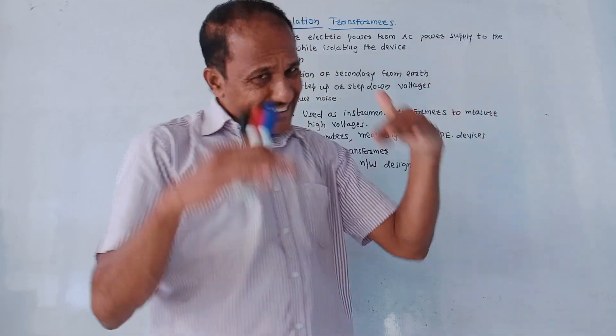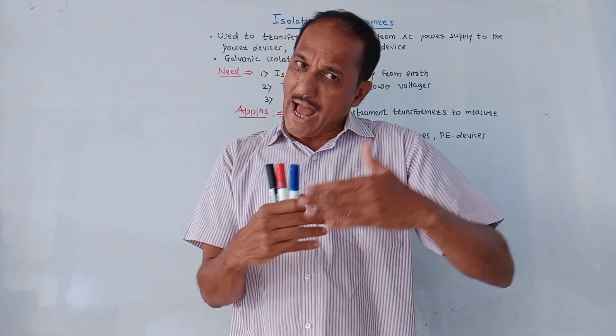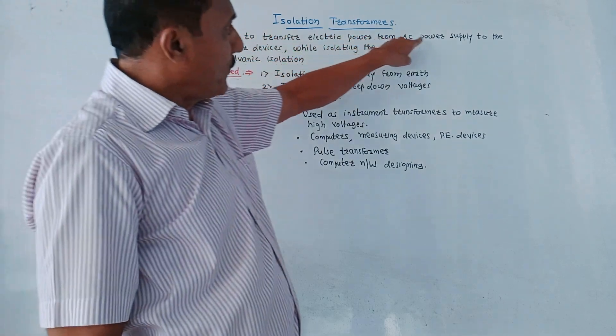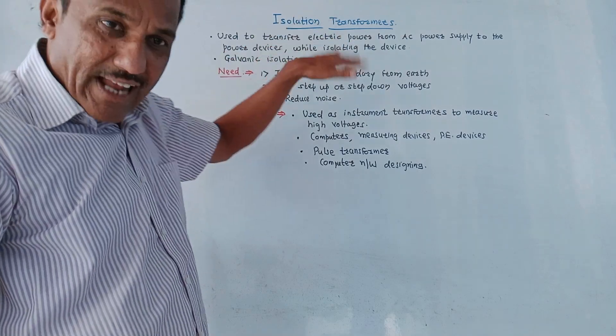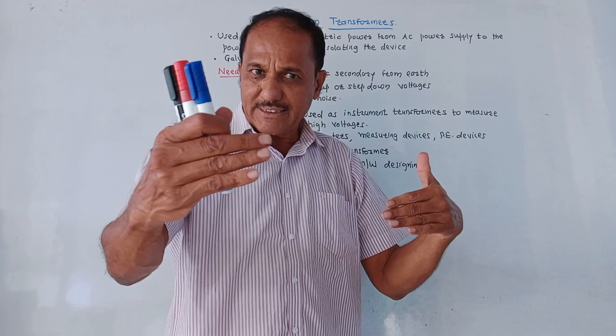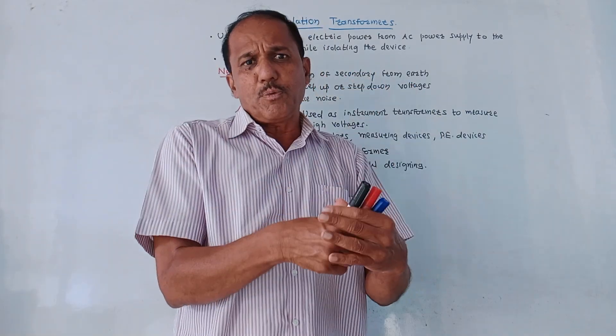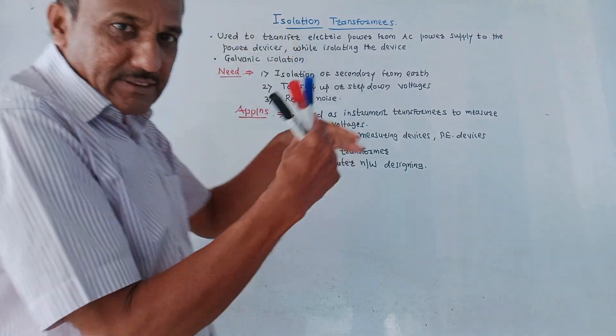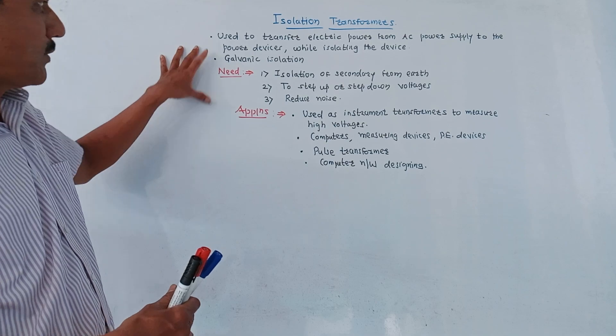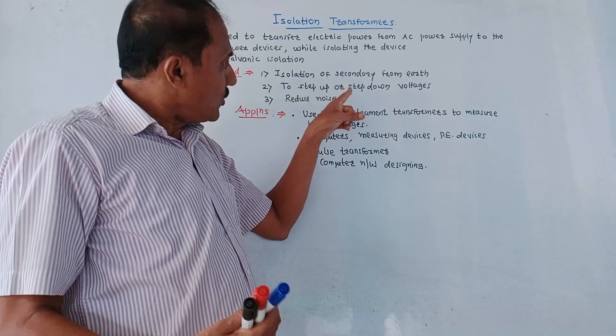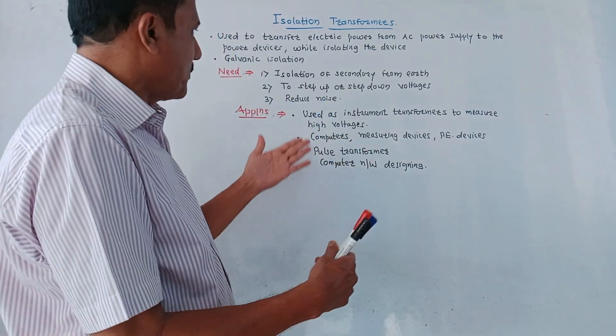Next is isolation transformers. As the name indicates, these are transformers used to isolate the power devices from AC mains. They transfer electric power from an AC power supply to the power devices while keeping the devices isolated. Like a normal transformer, it has primary and secondary windings with no physical connection between them — this provides galvanic isolation. The need for an isolation transformer is to get isolation of secondary windings from earth, it can be used as step-up or step-down, and an important advantage is to reduce down the effect of noise.